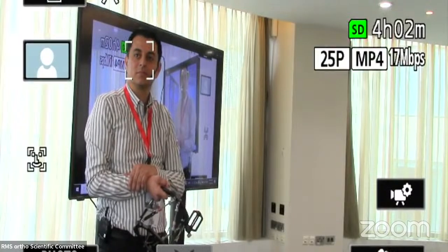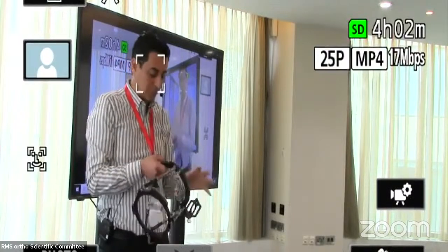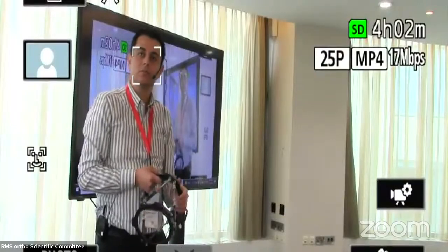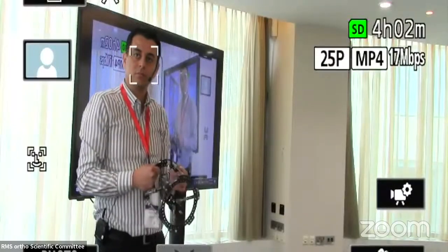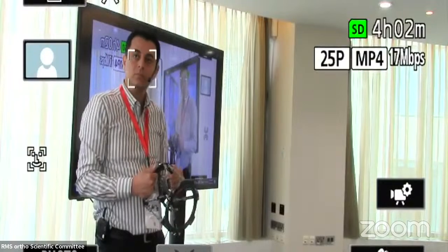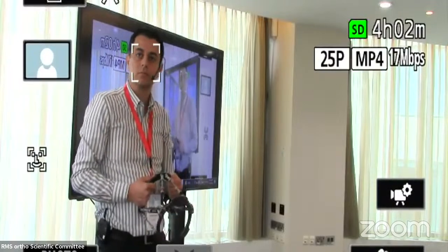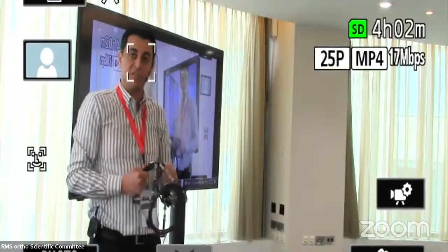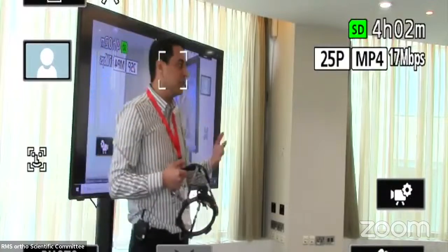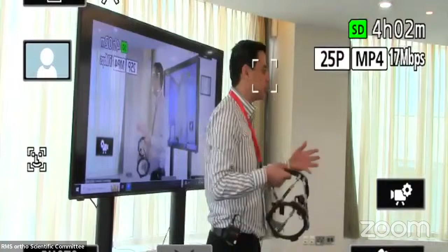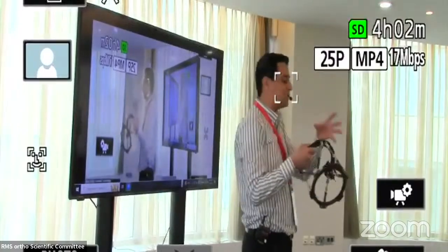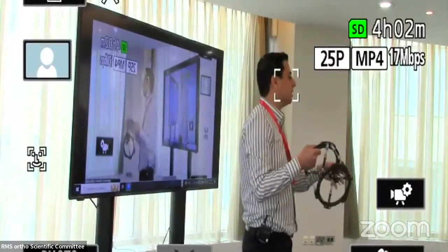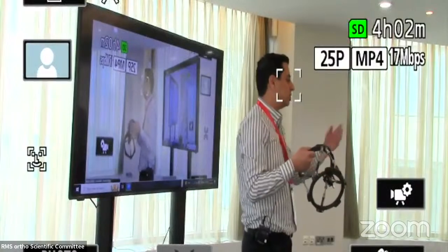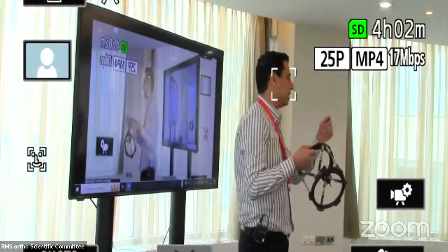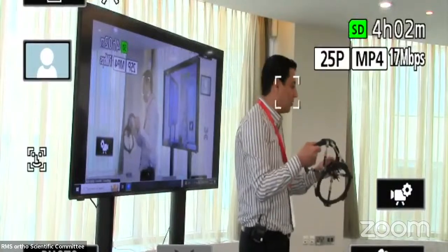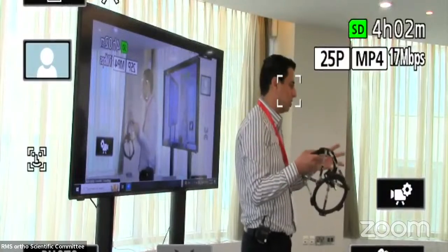But now they have to learn to get the beacon on the X-ray. Yes. Because before, they would just have the frame, and then the beacon would get lost off the side. Now we're saying, you've got to get the beacon on the X-ray. And still we are repeating the X-ray. So we sometimes need at least 5, 6 times to get the right image, because the system will not accept the image if it is not right. It will tell you that it cannot analyze. You need to make a new image with the beacon there.